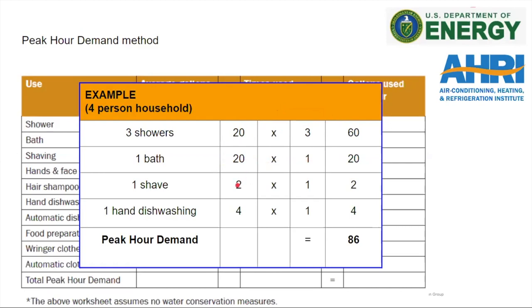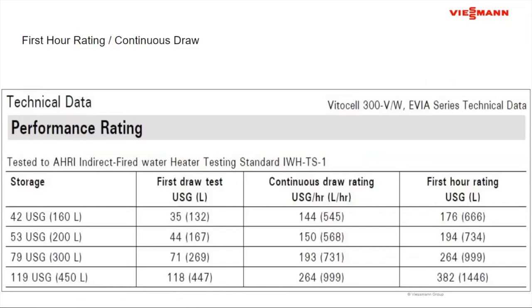Somebody's going to shave, and we're going to do hand dishwashing one time. So I get 4 gallons off the hand dishwashing, I get 2 off the shave, I add it all up, there's 86 gallons. That's the peak demand based on the anticipated usage. So you see the rules of thumb aren't very far off for this example, okay? So now I know, from the aspect of how much water has to be delivered in that first hour, I need 86 gallons, okay? So if I come in here back to my tanks, my three different sizes, I'm going to go over here to the first hour rating.